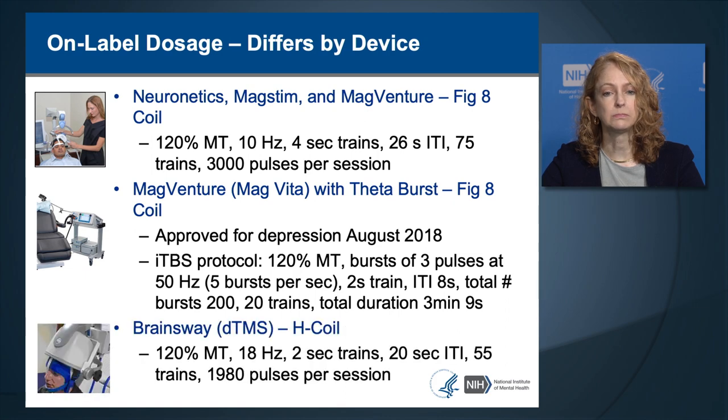The on-label dosage for the BrainSway deep TMS coil, also called the H-coil, is 120% of motor threshold, 18 hertz, 2-second trains, 20-second inter-train interval, 55 trains per session, and a total of 1,980 pulses per session. It's important to use the right dose for the right manufacturer; the on-label dose is found in the Operator Manual.